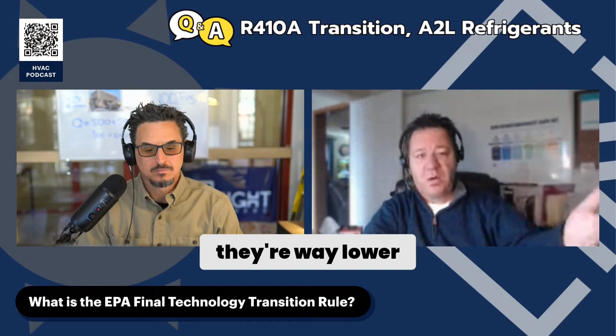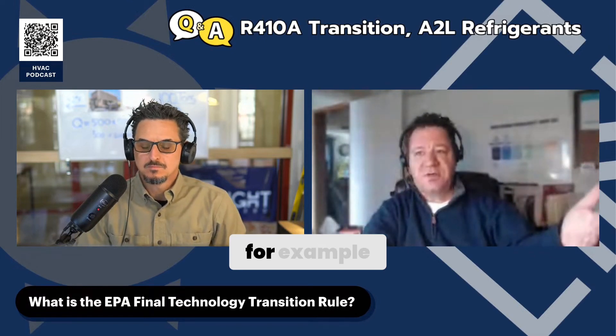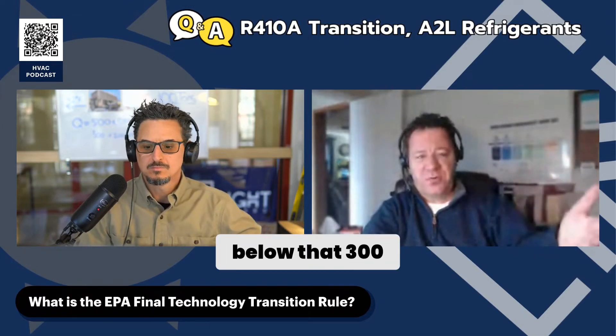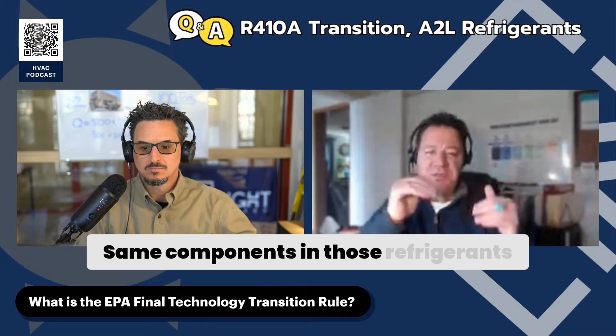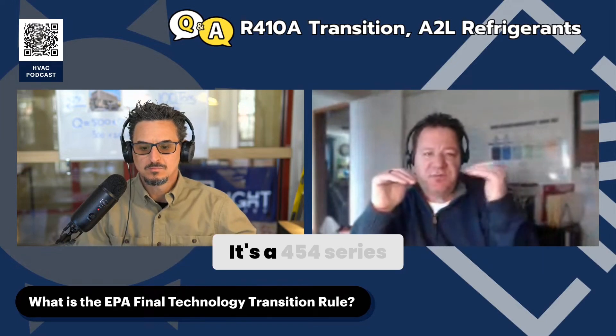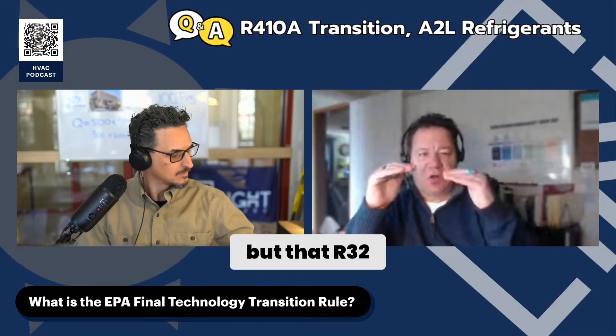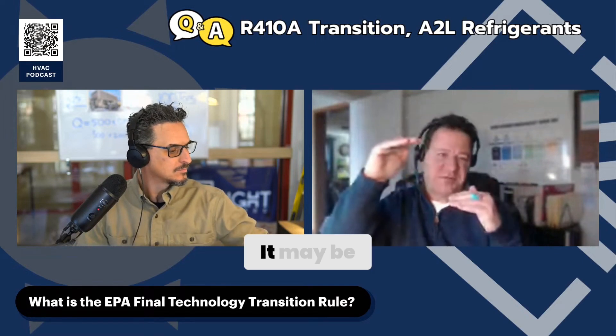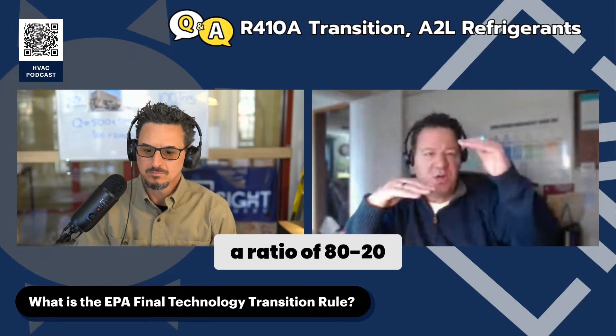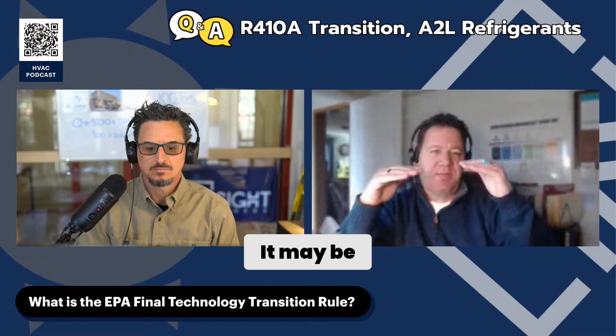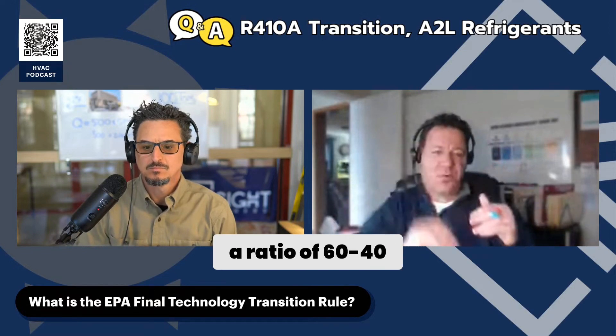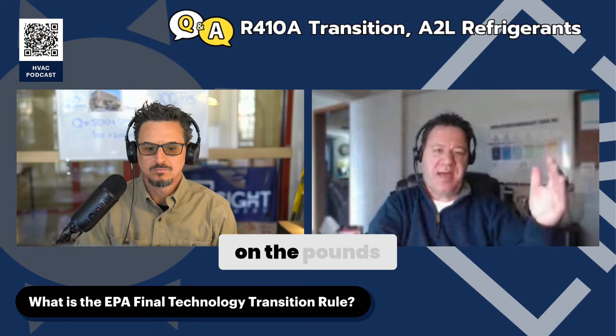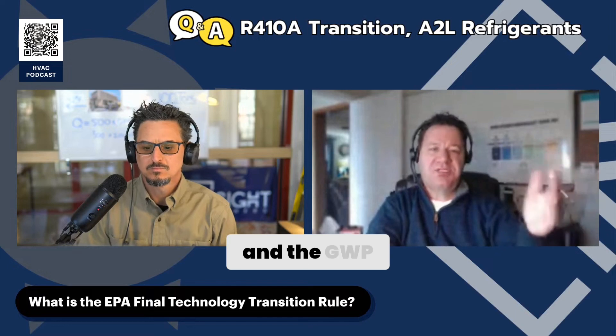When I say lower, they're way lower — 454A, for example, is 238 GWP, so it's well below the 300 limit. It's the same components in the 454 series refrigerants, but that R32 and 1234YF ratio shifts. It may be 80/20, 50/50, or 60/40. Each one can fit a different application based on the pounds and GWP requirements.